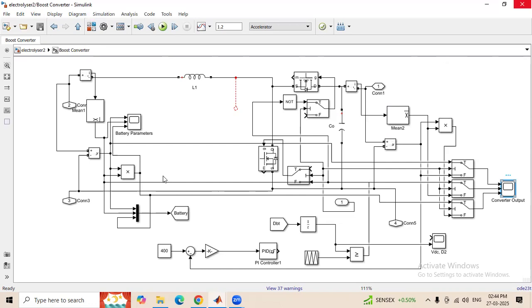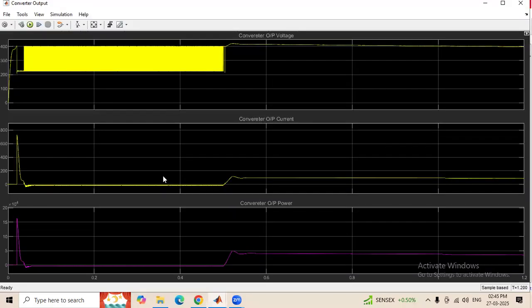The voltage across the converter while the battery is charging is 240 volts, which is the battery voltage. When the battery is discharging, 400 volts is the output of the converter. So it oscillates: when charging, 240 volts is the output; when discharging, 400 volts is the output. In this stage, the battery is continuously switching between charging and discharging modes.